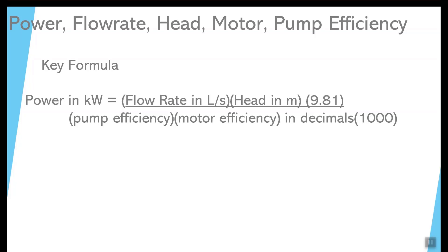Multiply those three numbers together on the top to get an answer. The bottom of the fraction is the pump efficiency in decimals — so 89% would be 0.89 — times the motor efficiency, so 80% would be 0.80. Multiply those together, then multiply by 1,000 to get the bottom number. Then divide the top answer by the bottom answer to get your final answer.